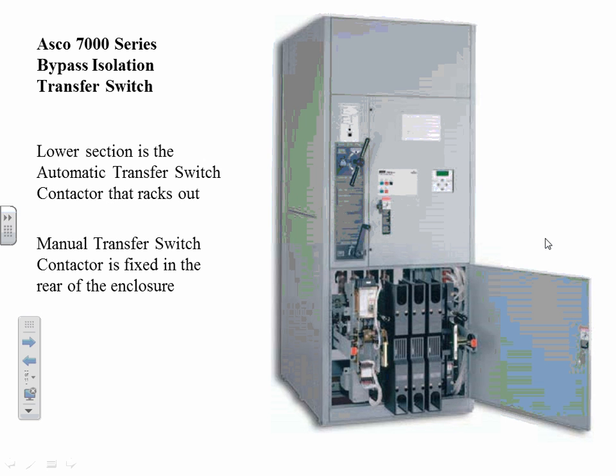Here's what they actually look like. Again, you've got rails down here on the bottom. This is the automatic transfer switch contactor here. This is the operational arm for the manual transfer switch. So you rotate that to operate the switch manually. This is the crank out here to actually rack it out and get it out of the operation. And you can see from the physical size, it's big. This is a 90-inch cabinet. There's another set of contactors that you don't see that are in the back here that are being operated again by that handle. Bypass isolation transfer switch.